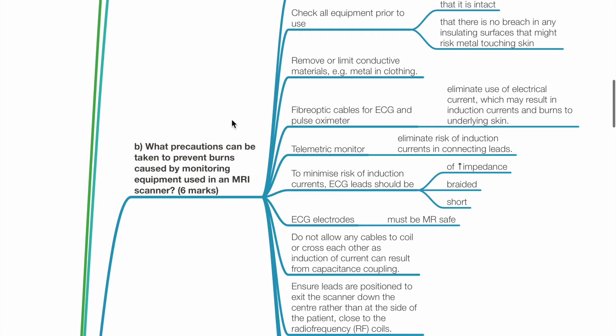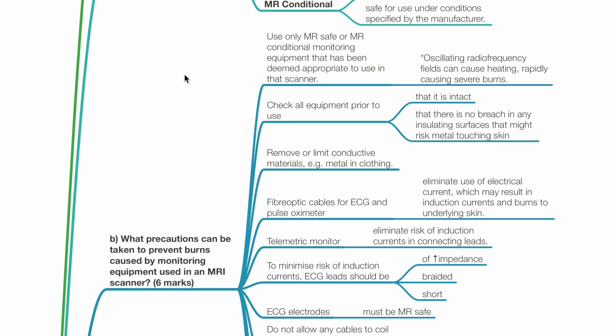Part B: What precautions can be taken to prevent burns caused by monitoring equipment used in an MRI scanner? Use only MR-safe or MR-conditional monitoring equipment deemed appropriate for that scanner. Check all equipment prior to use to ensure it is intact and there is no breach in any insulating surfaces that might risk metal touching skin.